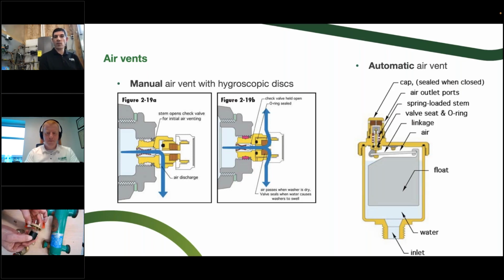So that little linkage there, when the air comes up, it's going to push the float down, pull the needle down, and allow some air out. As soon as it's full, then the water level goes up and it closes that little needle valve. So if you pull that linkage apart, you can service that really easily. The one thing to note is when you put it back together, make sure that linkage goes back onto the pin, and you even hear a little click there, so it engages the needle. If you don't get that on like that, then it's going to float without moving the needle, and that's not what we want. So Cody, do you want to tell us what's important about the air pocket up at the top there? For sure, for sure.